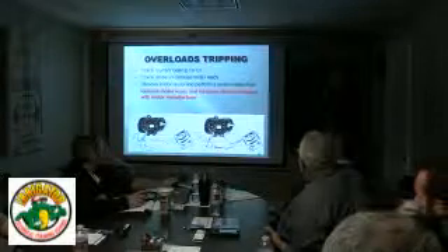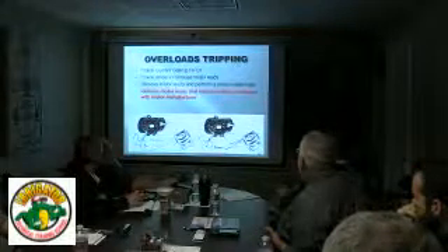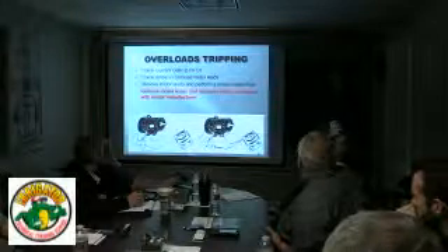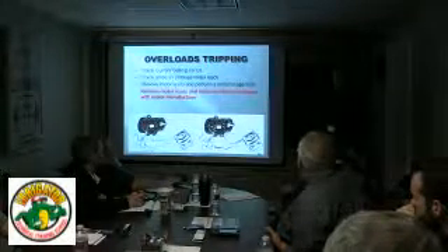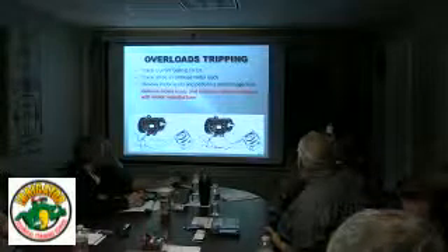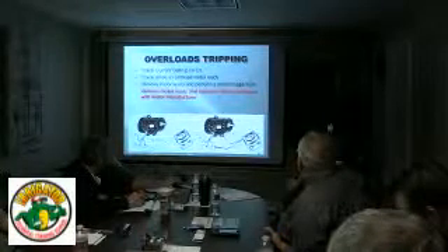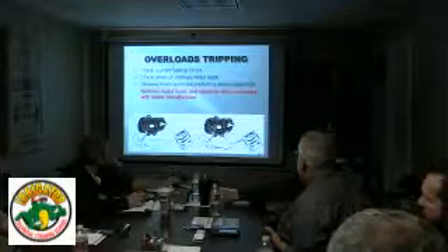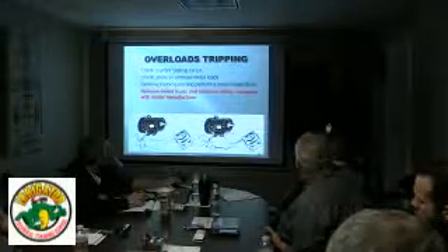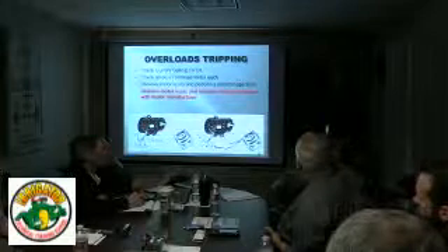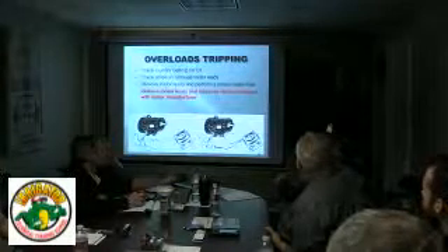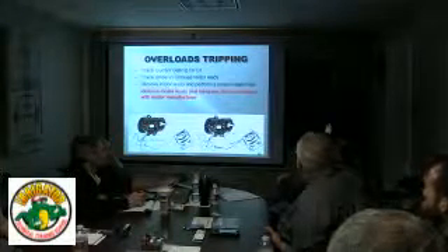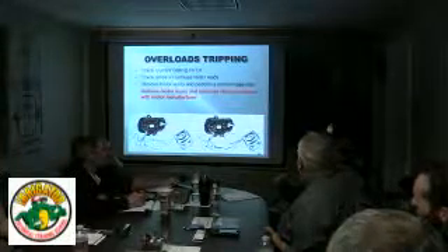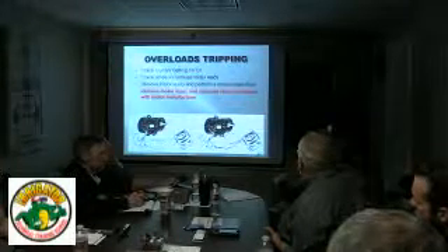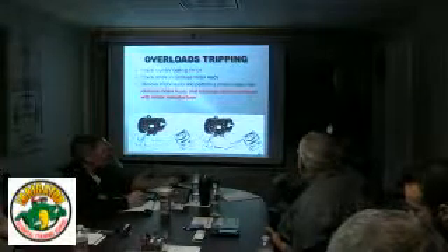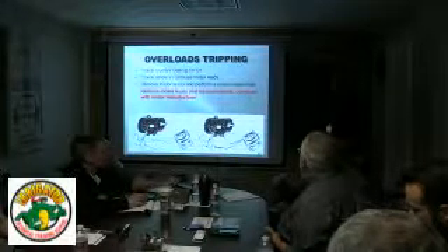Or you can remove the motor leads and measure the ohms, compare with the motor manufacturer. A lot of times you have no idea what it is, or you don't have the manual, and they range in such a big range from motor manufacturers to the different types of motors. A bigger 6-inch submersible might be as high as 12 ohms. I think a half horsepower submersible is like .007 or something, or no, it's the other way around. They can be as low as .07, or a half horse submersible is like 38 ohms.